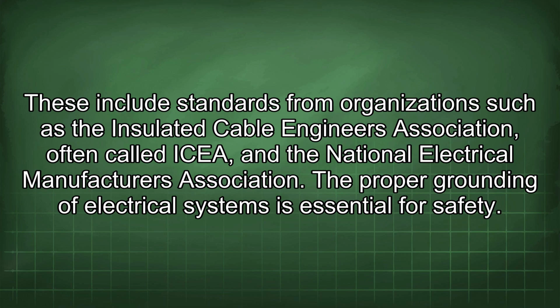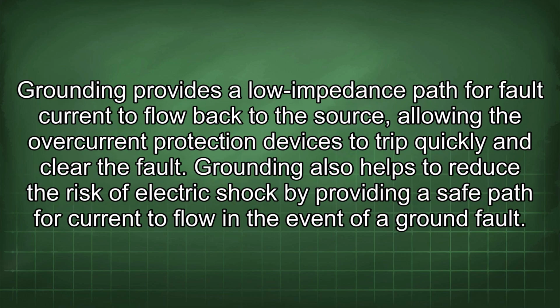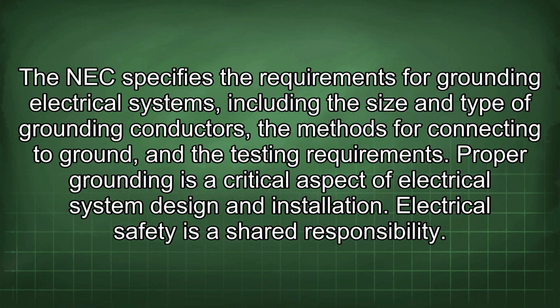The proper grounding of electrical systems is essential for safety. Grounding provides a low impedance path for fault current to flow back to the source, allowing the overcurrent protection devices to trip quickly and clear the fault. Grounding also helps to reduce the risk of electric shock by providing a safe path for current to flow in the event of a ground fault. The NEC specifies the requirements for grounding electrical systems, including the size and type of grounding conductors, the methods for connecting to ground, and the testing requirements. Proper grounding is a critical aspect of electrical system design and installation.